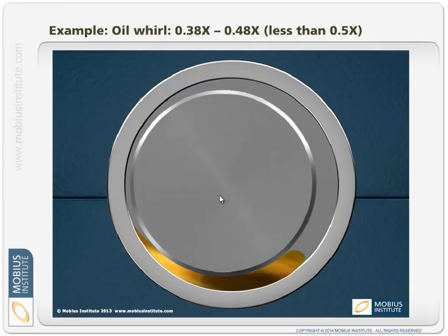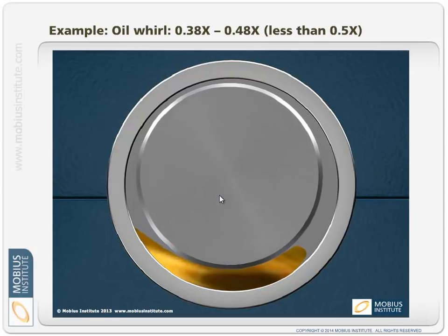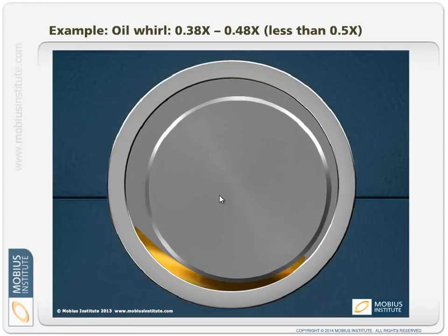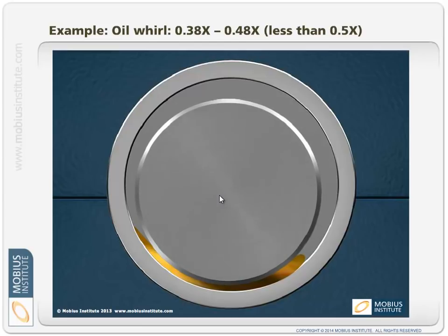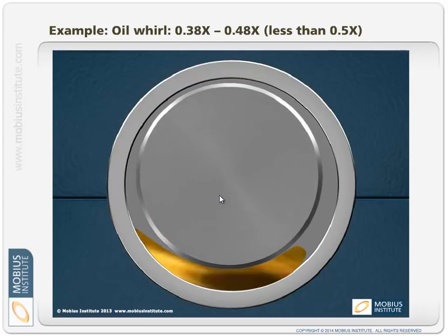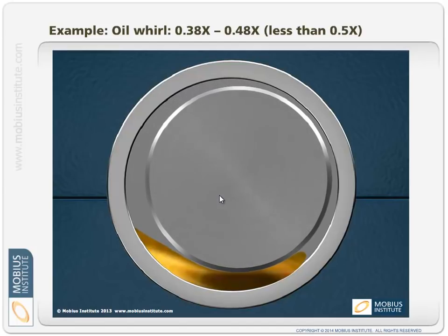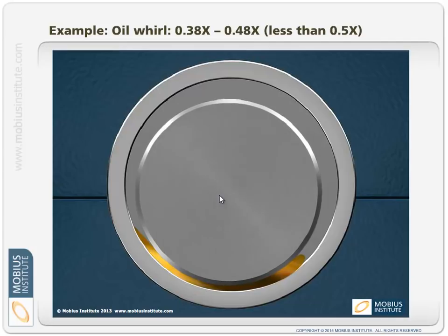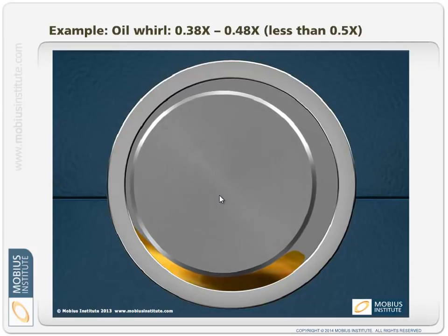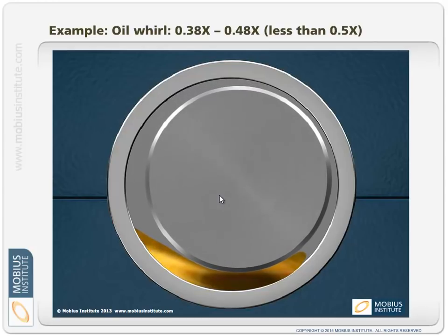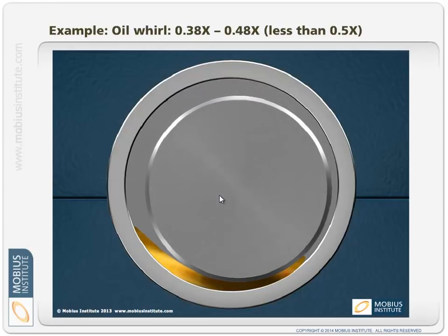But you can see there's a very dominant motion. Now, remember, a shaft is being influenced by a lot of things. So there might be both a 1x motion superimposed on, or the other way around, this high amplitude, lower frequency, subsynchronous vibration. And the proximity probe's picking up the entire motion, but from a frequency point of view, we can see that some of it's low frequency and some of it's at 1x.